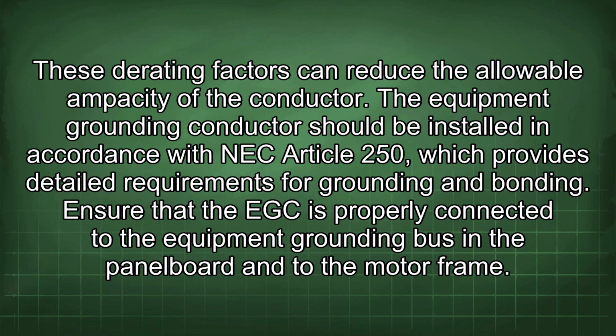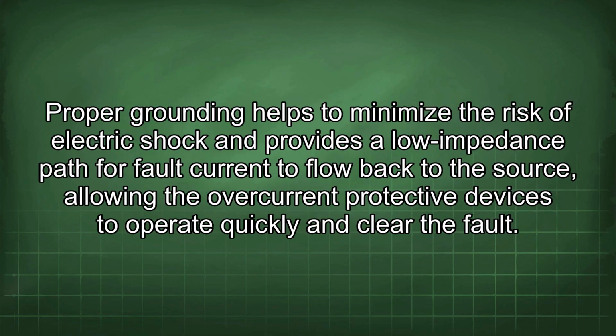The equipment grounding conductor should be installed in accordance with NEC Article 250, which provides detailed requirements for grounding and bonding. Ensure that the EGC is properly connected to the equipment grounding bus in the panel board and to the motor frame. Proper grounding helps to minimize the risk of electric shock and provides a low impedance path for fault current to flow back to the source, allowing the overcurrent protective devices to operate quickly and clear the fault.